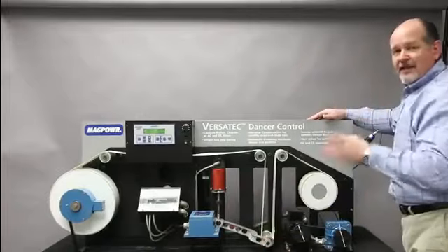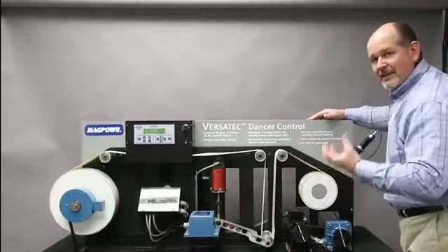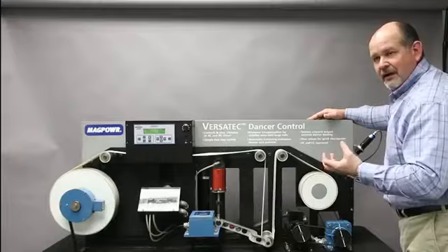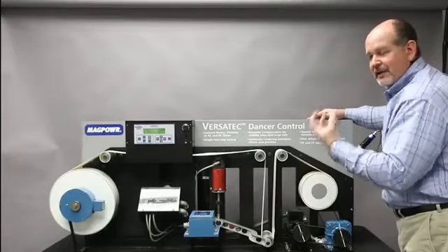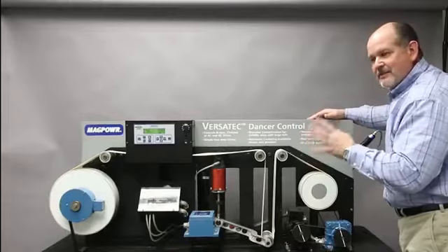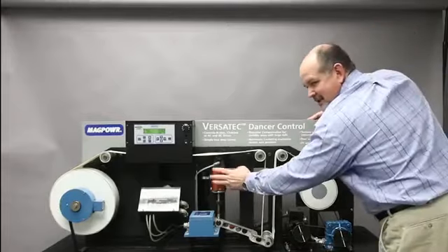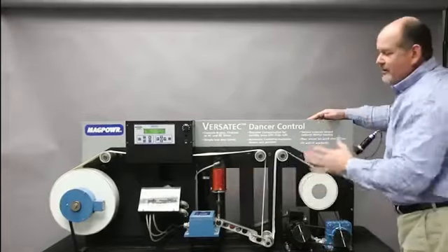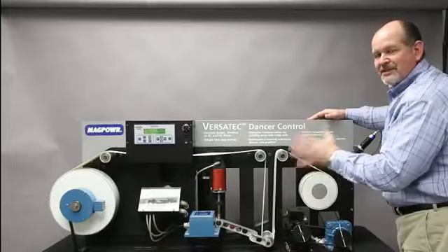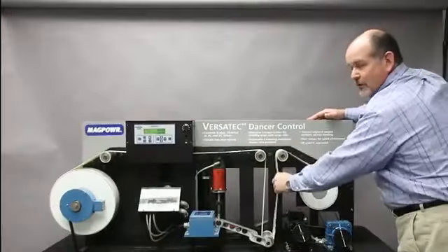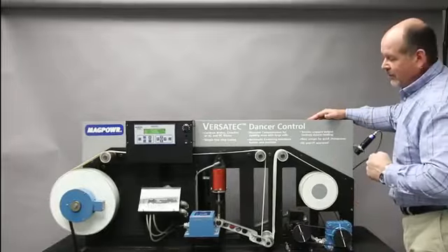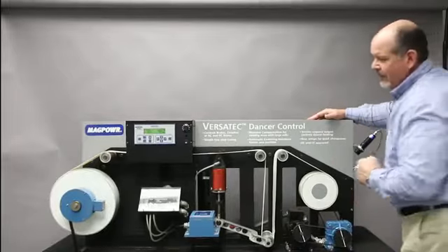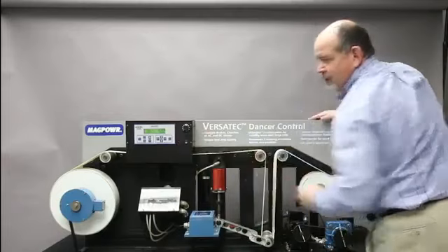Okay, so that's critical, because if you use a piston type or an O-ring type, it can actually stick, and there's a breakaway force, and all of a sudden it moves freely, then sticks. Those types of things, since this is the tension, this is the load in the dancer, those transients or those sticking points will introduce tension spikes into the web. So it's very important to use a low friction type cylinder. Now let's back up and let's go to the control itself.